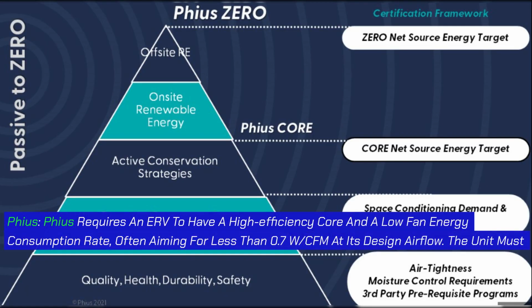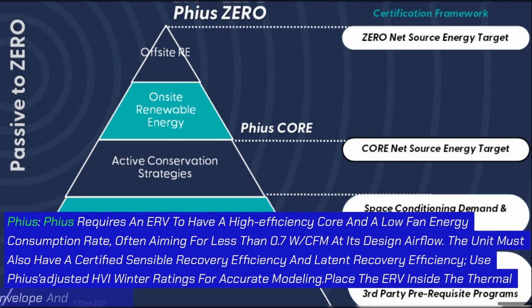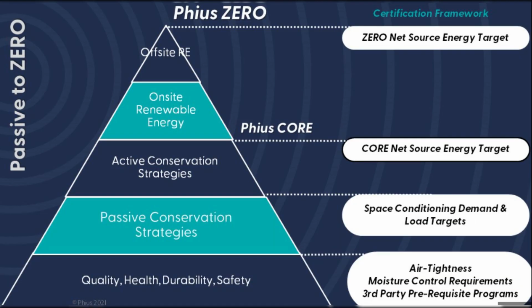Certification expectations for ERV: Phius. Phius requires an ERV to have a high-efficiency core and a low fan energy consumption rate, often aiming for less than 0.7 W/CFM at its design airflow. The unit must also have a certified sensible recovery efficiency and latent recovery efficiency. Use Phius-adjusted HVI winter ratings for accurate modeling.